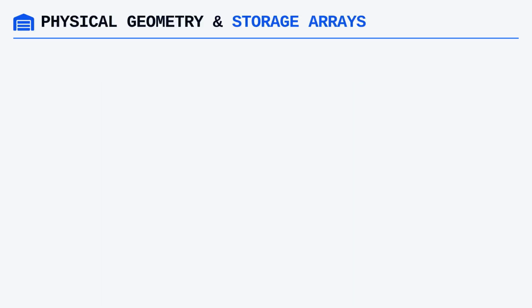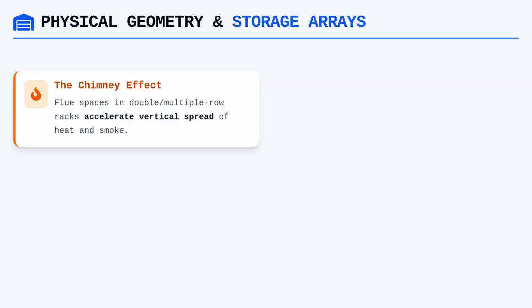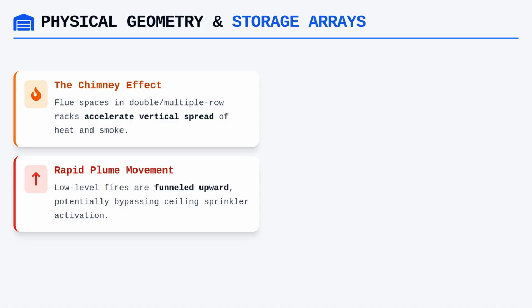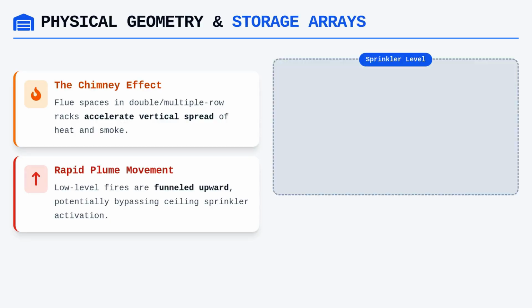Once we determine the fuel characteristics, we must turn our attention to the physical geometry of the storage arrays themselves. The movement of fire plumes through vertical and horizontal flue spaces is a complex fluid dynamics problem that often baffles those unfamiliar with rack storage. In double row or multiple row rack configurations, these flue spaces act as chimneys, accelerating the vertical spread of heat and smoke. If a fire starts at the lower levels of a high-piled rack, it is immediately funneled upward, bypassing the ceiling-level sprinkler activation threshold unless we design the path correctly.